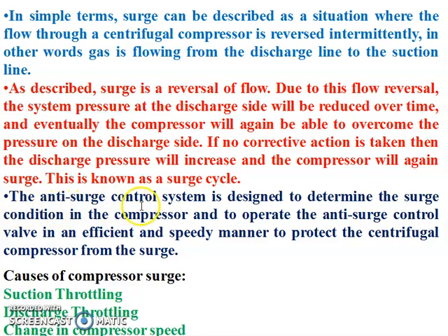The anti-surge control system is designed to determine the surge condition in the compressor and to operate the anti-surge control valve in an efficient and speedy manner to protect the centrifugal compressor from surge.